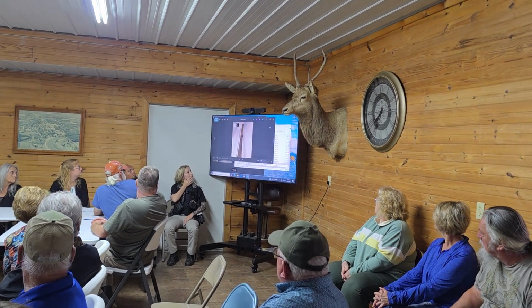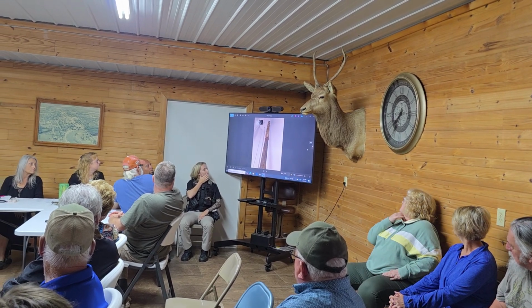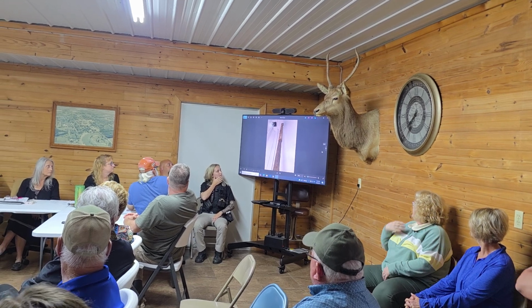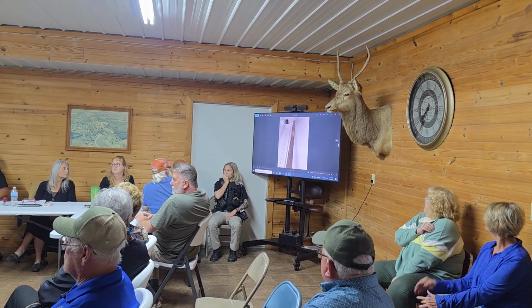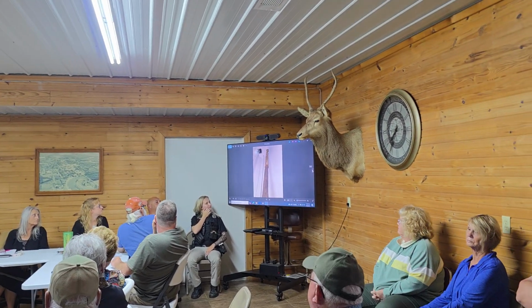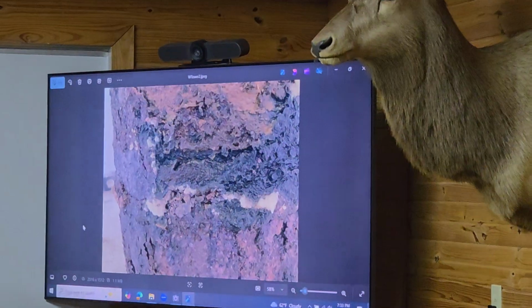What kind of price are we looking at? This is the actual pipe in question here, and the insulation is just left there for you to see how it really is surrounded. But in some of our opinions, the insulation has caused the water to be trapped on the pipe and cause some of this corrosion. Temperature change. Yeah, it's almost rusted.